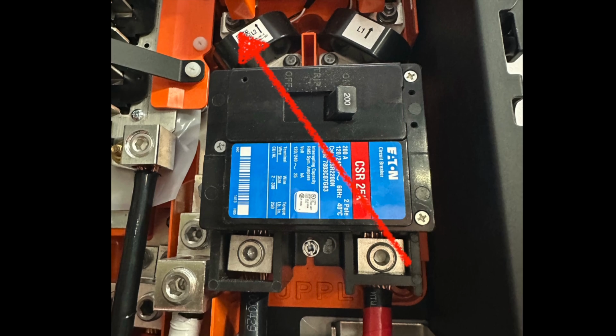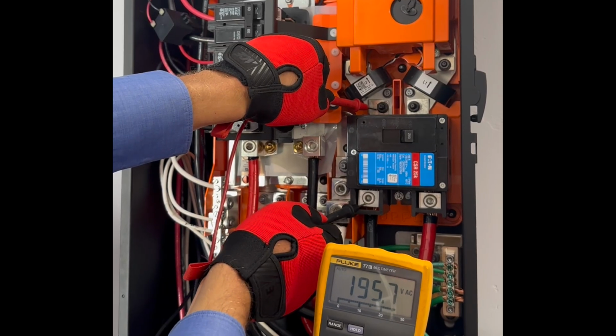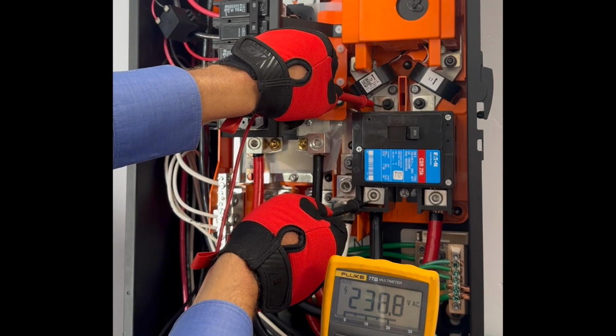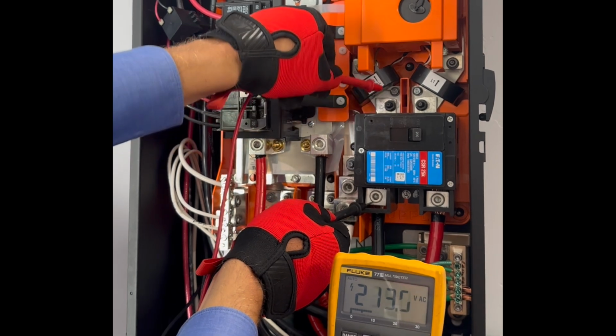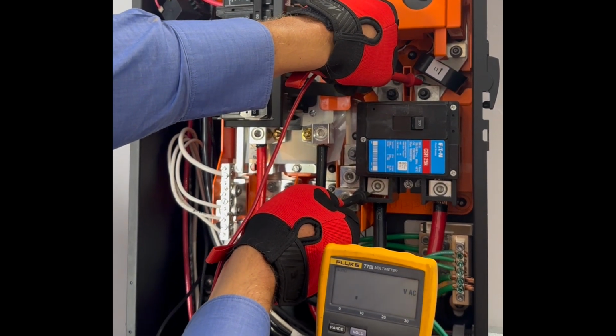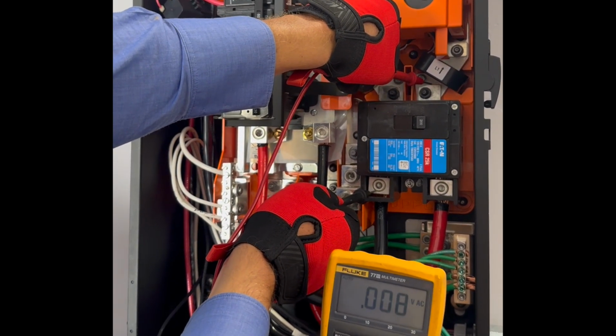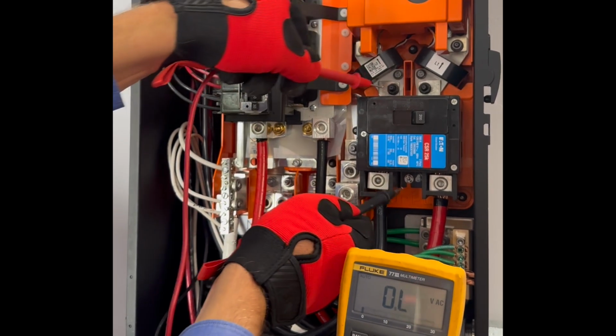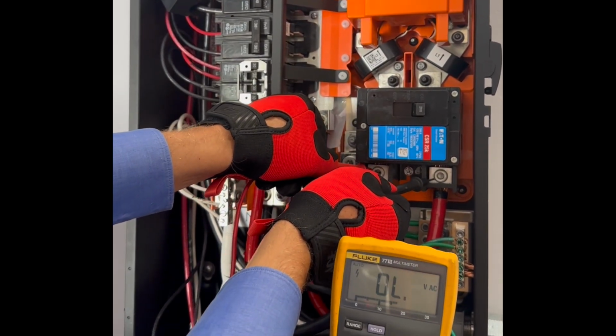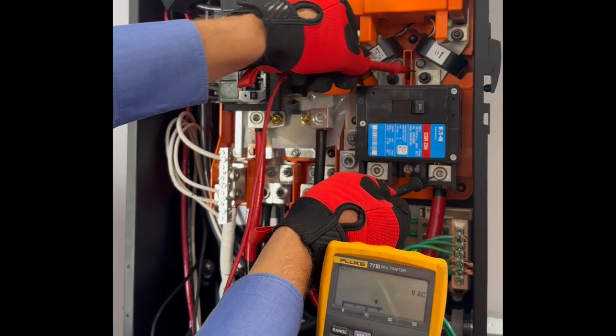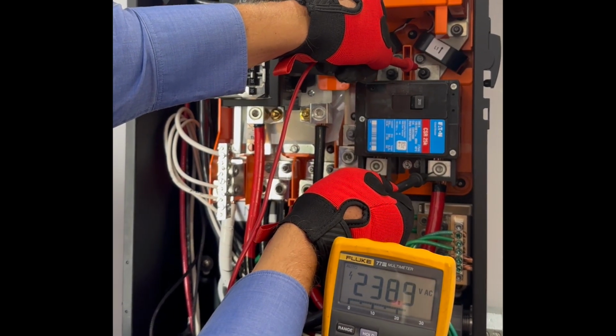Look, straight up through the breaker shows a 240 volt difference. That's what you see when measuring across the two different phases. And crossing the breaker shows no voltage difference. That's what you get across a continuous wire. I hadn't encountered a breaker that does this before, so this was confusing to me, but anyway, that explains it.